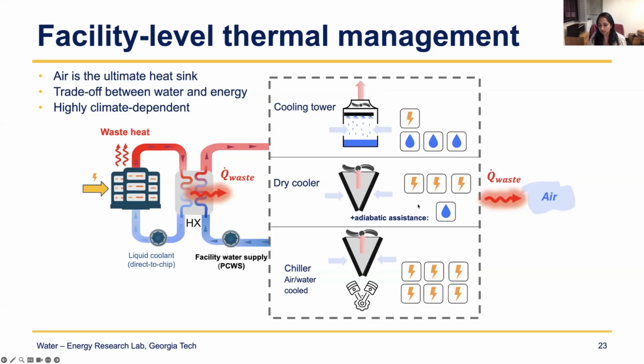So we're looking at dry cooling, where essentially it's just like a large car radiator, with a fin tube heat exchanger, and you're consuming power for the fans to blow air through it, but very little water, only in the form of what we call adiabatic assist, like a little water spray or a soaked pad to pre-cool the air in certain locations.